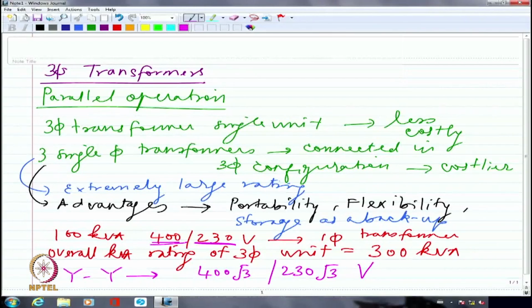So when I calculate the current, I can take the overall kVA rating divided by root 3 times VL, where VL is the line voltage. Or if it is star, I know for sure, I can definitely calculate the single phase current also. That will go as the 3-phase line current as well. If it is delta, of course I have to multiply the per phase current by root 3, right? So I should be able to easily calculate the 3-phase unit's rating in terms of voltages and currents based on what connection I am making. So let us say I have one single phase unit, something like this.